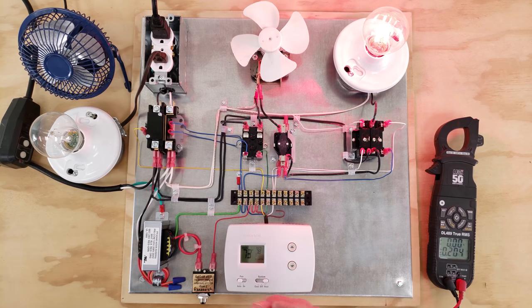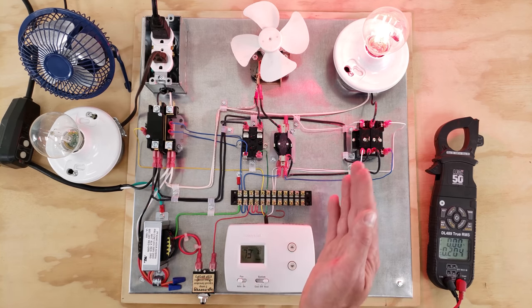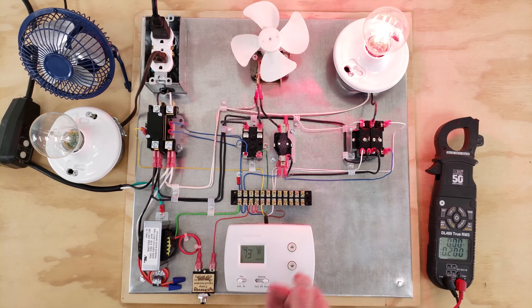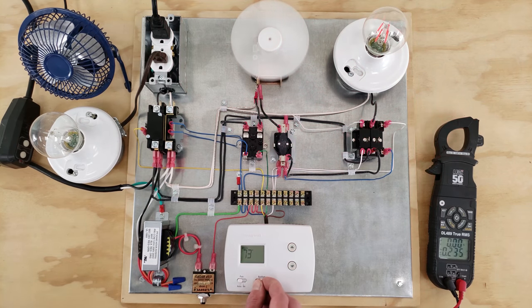We would ask the customer, hey, what's going on with this system? What's the problem? So we would do that first, then test the system like we're doing right now. We're turning the heat on. We want to make sure that the fan turns on and make sure that the air conditioning turns on as well. All right, so the heat works fine, so that's great.